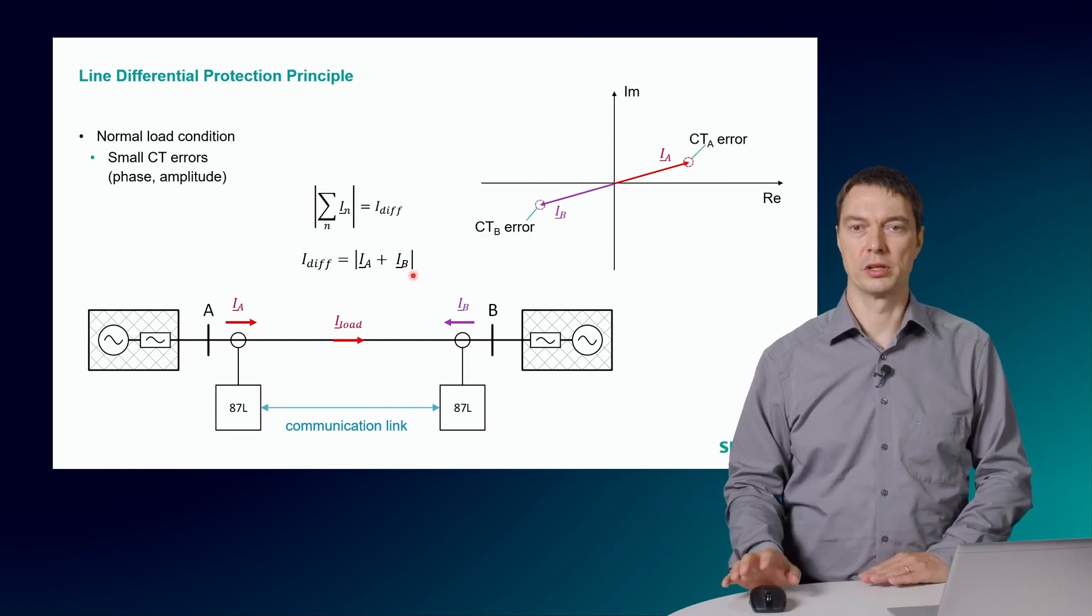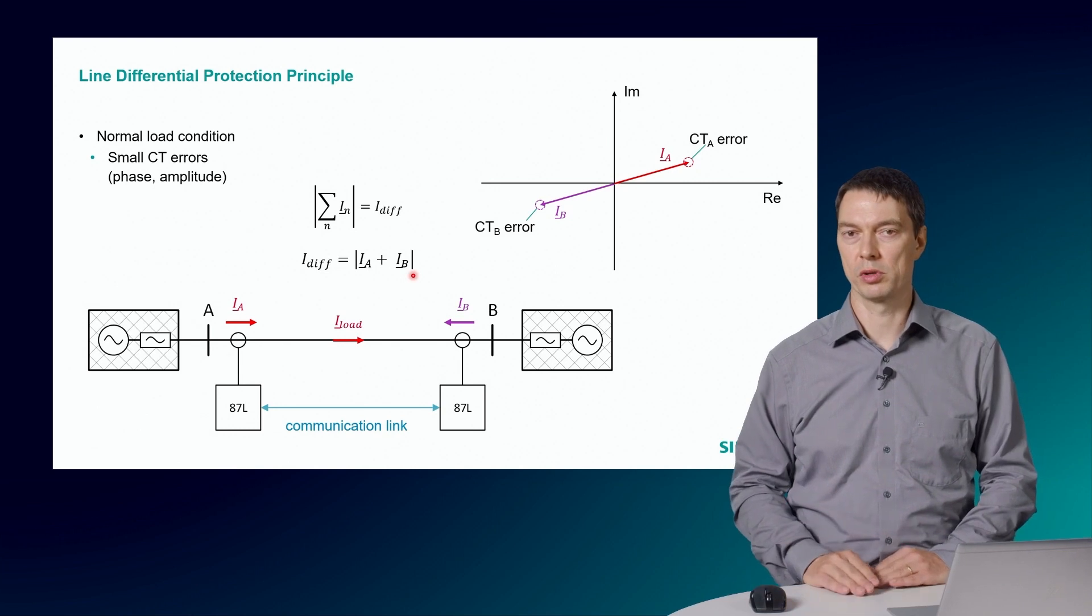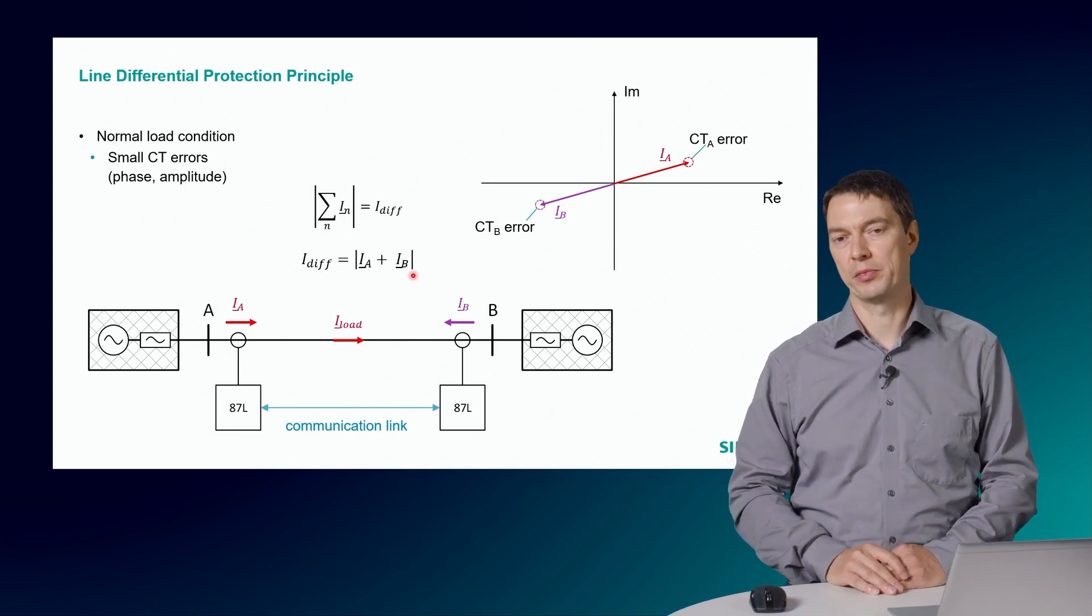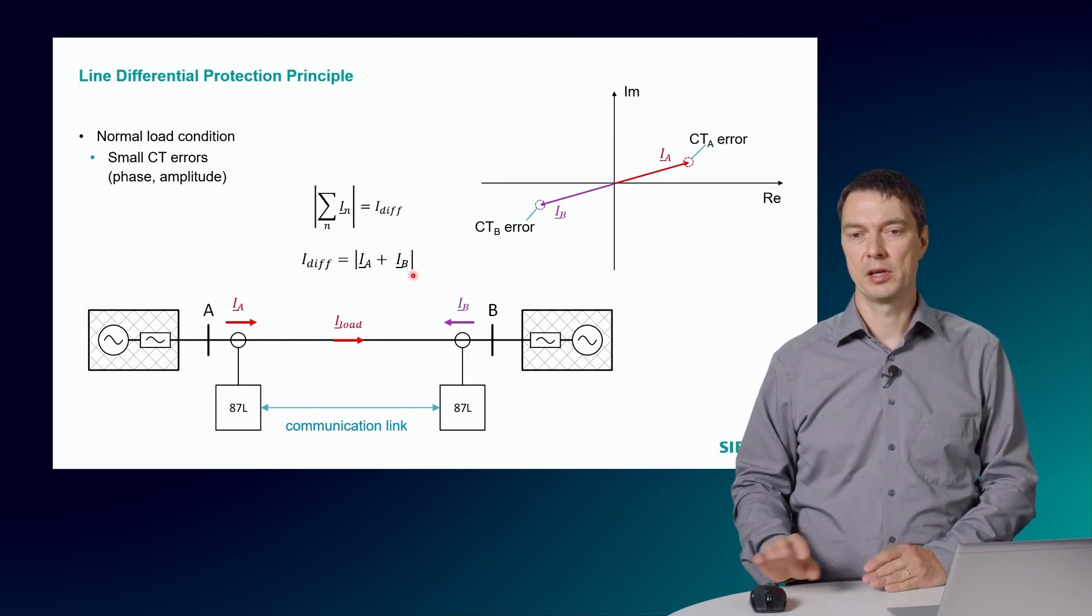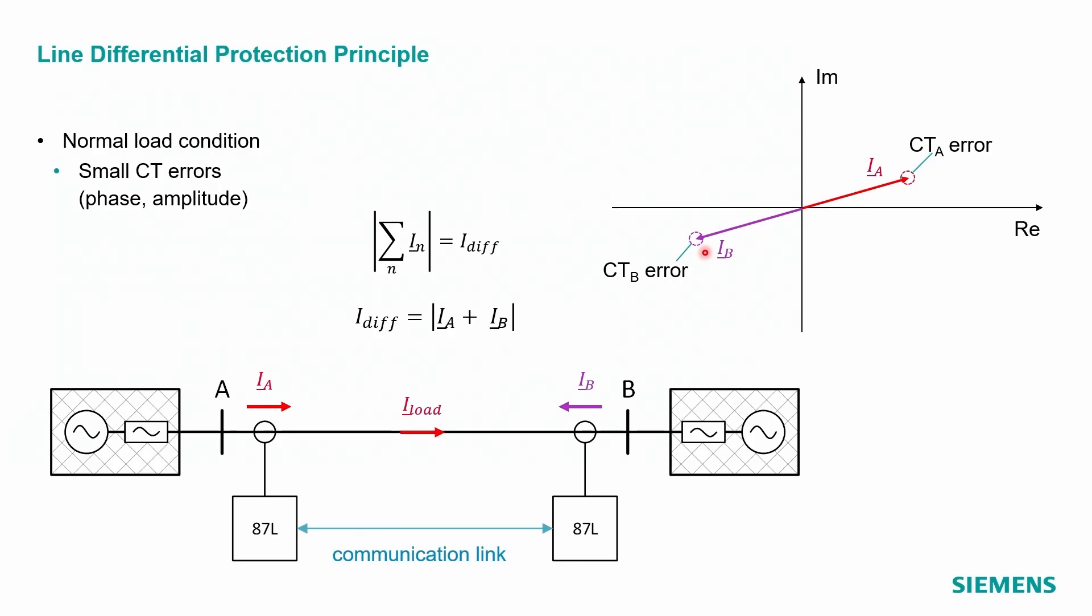This is the ideal condition. In reality, the CTs will have some small errors, which will result in an error in the amplitude in the phase, which is shown in the figure here with some small circles on the top of these phasors. The differential current as the sum of both current phasors will result in a very small differential current. The small differential current needs to be considered in the relay settings.